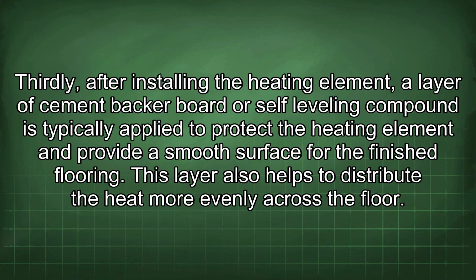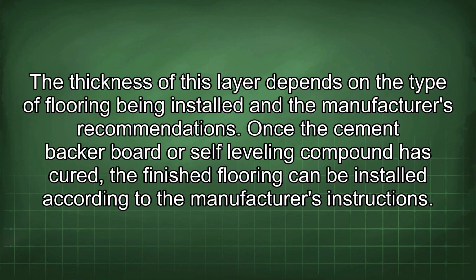Thirdly, after installing the heating element, a layer of cement backer board or self-leveling compound is typically applied to protect the heating element and provide a smooth surface for the finished flooring. This layer also helps to distribute the heat more evenly across the floor. The thickness of this layer depends on the type of flooring being installed and the manufacturer's recommendations.